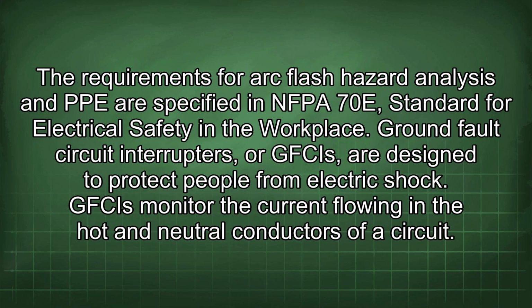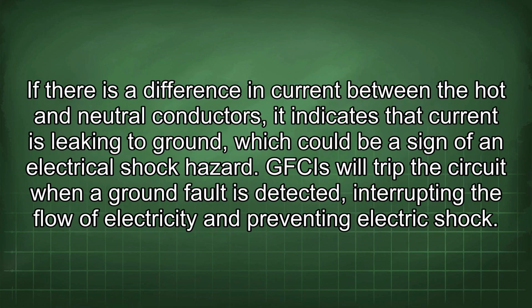The requirements for arc flash hazard analysis and PPE are specified in NFPA 70E, Standard for Electrical Safety in the workplace. Ground fault circuit interrupters, or GFCIs, are designed to protect people from electric shock. GFCIs monitor the current flowing in the hot and neutral conductors of a circuit. If there is a difference in current between the hot and neutral conductors, it indicates that current is leaking to ground, which could be a sign of an electrical shock hazard. GFCIs will trip the circuit when a ground fault is detected, interrupting the flow of electricity and preventing electric shock.